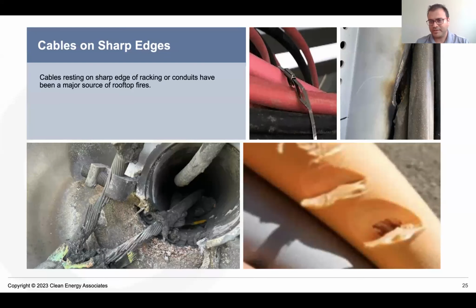The picture on the top right is from another site we were inspecting, an example where we averted a major issue just in time. When we start an investigation, we ask the owners or developers to turn off the system completely to make sure we're safe. Then we start opening the enclosures to do a deep dive, or as Chris said, look under the hood of a car. We found this cable on the top right had been damaged while pulling cables during construction.